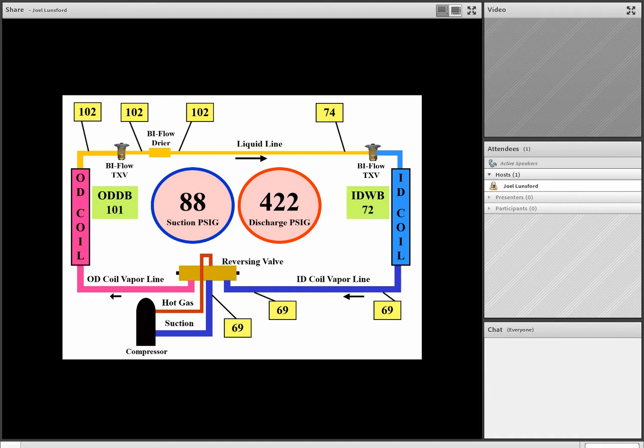Well, team, if you found on your diagnosing system problems another liquid circuit restriction, that is correct. But let's narrow that down some. As we take a look at the temperatures across the liquid line circuits, we have 102 degrees across the biflow TXV outdoor. That's normal. That's fine. We have 102 degrees across the biflow TXV outdoor and the biflow filter dryer. So there's nothing wrong with those components.